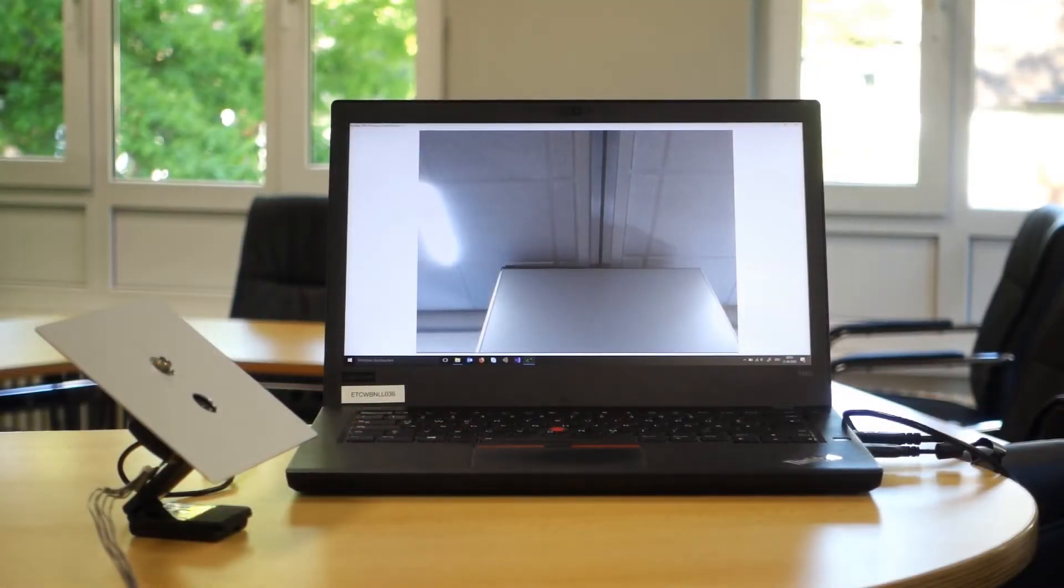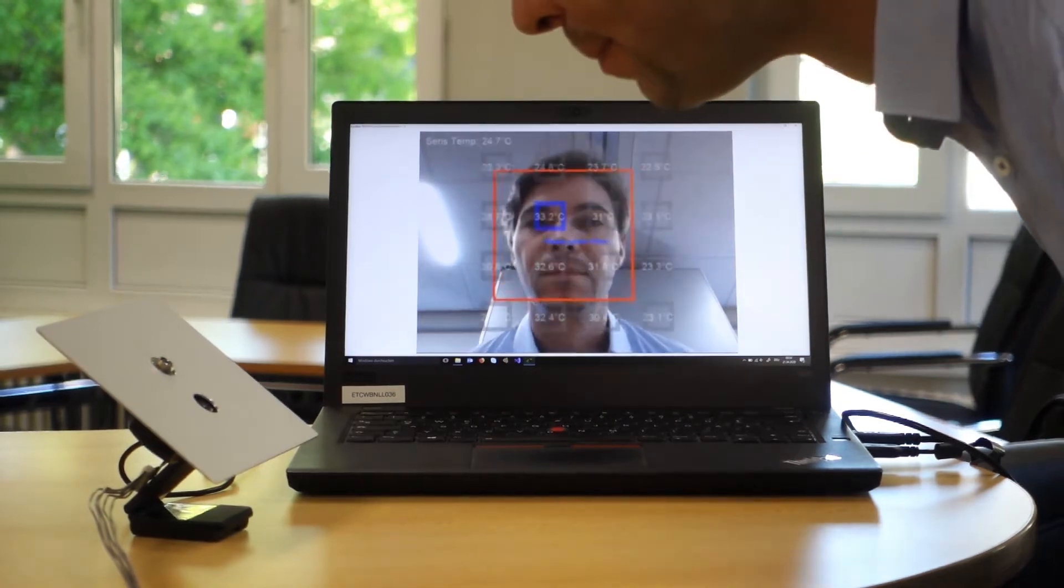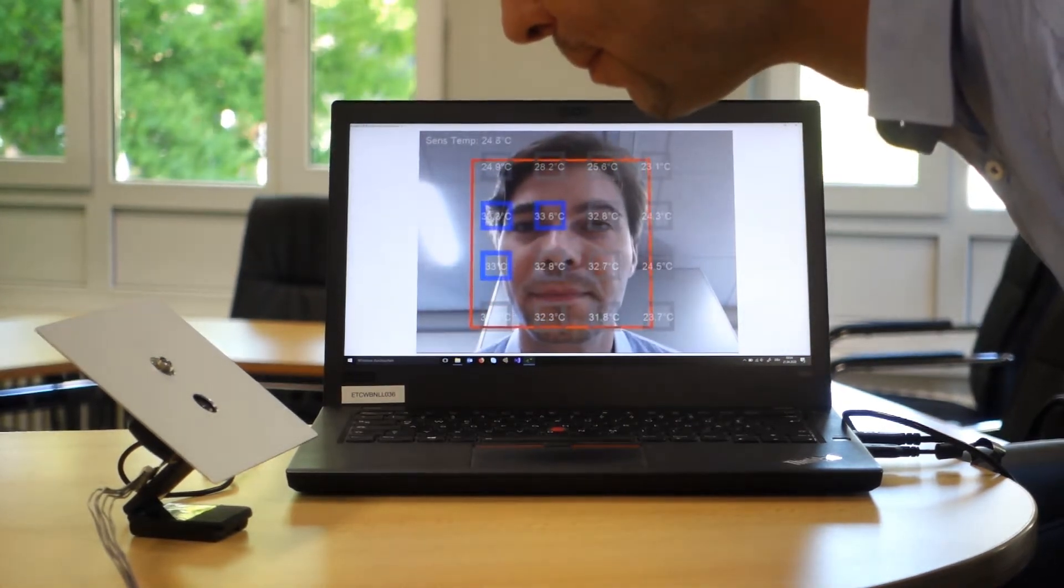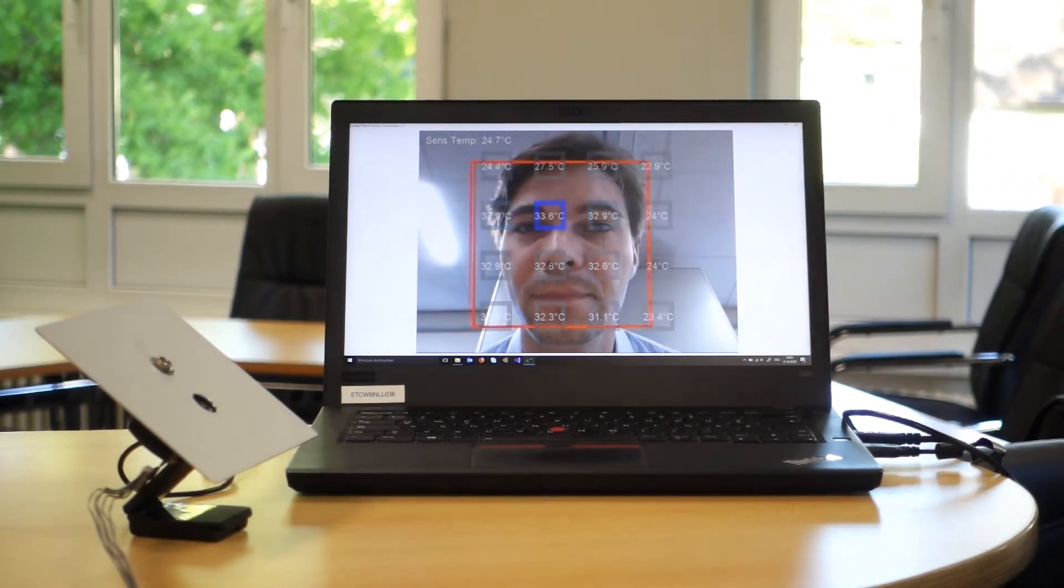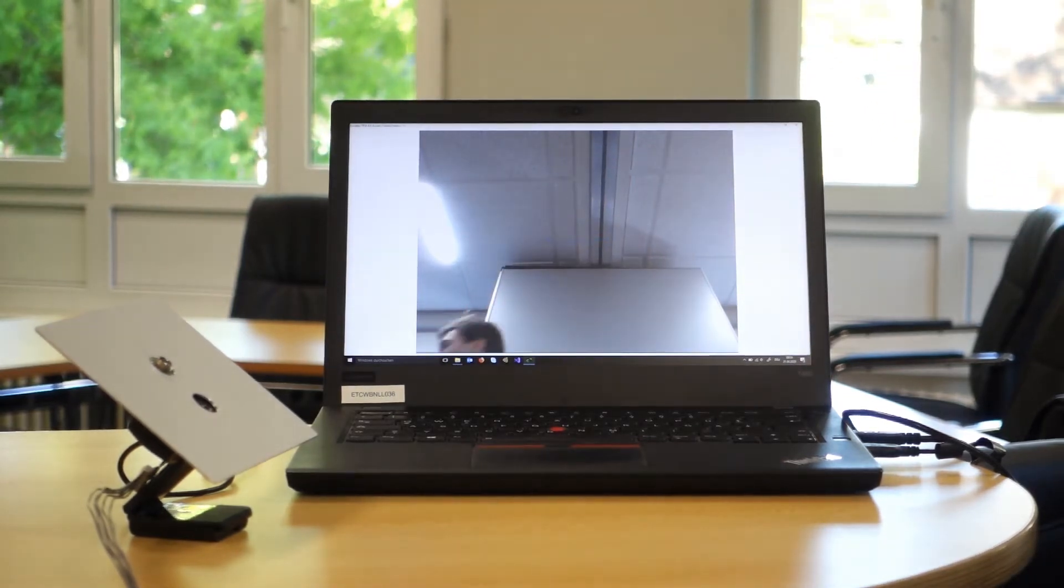But there are applications like human fever scanners where stock sensors will not perform as expected. You may not be able to constrain the target distance, and the bare sensors will show large variations in the sensor's temperature output.